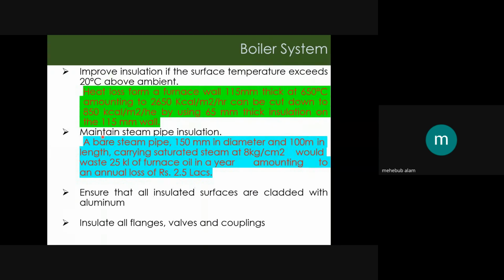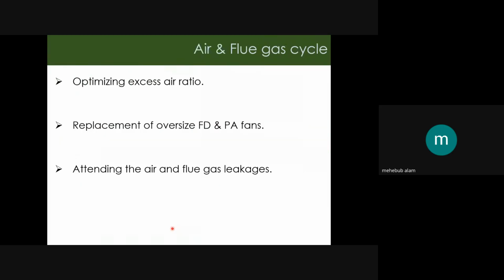Now we have to maintain the steam pipe insulation, because if the pipe insulation is not proper, there will be heat loss. For example, a bare steam pipe, 150 millimeter in diameter and 100 meter in length, carrying saturated steam at 8 kg per centimeter square, would waste 25 kiloliters of furnace oil in a year, and that amounts to rupees 2.5 lakhs. Ensure all insulated surfaces are cladded with aluminum, and we have to ensure that all flanges, valves, and couplings are insulated.